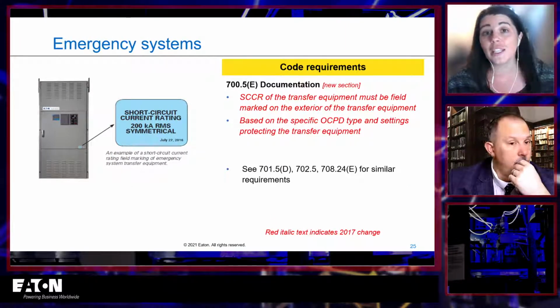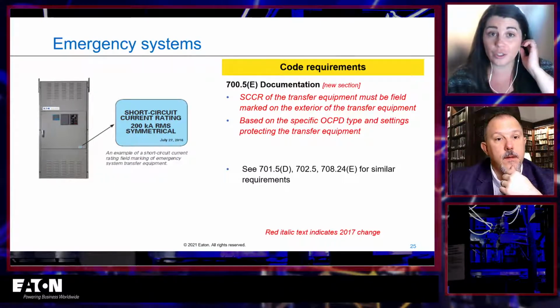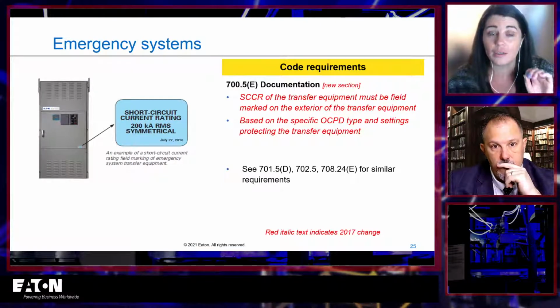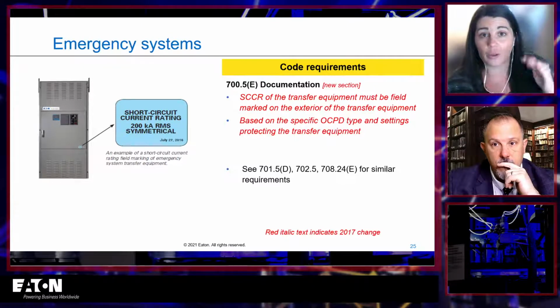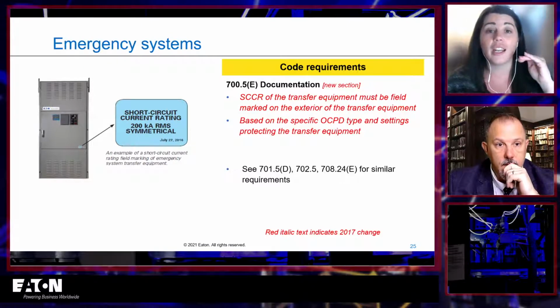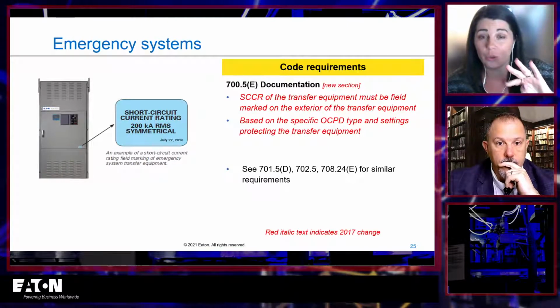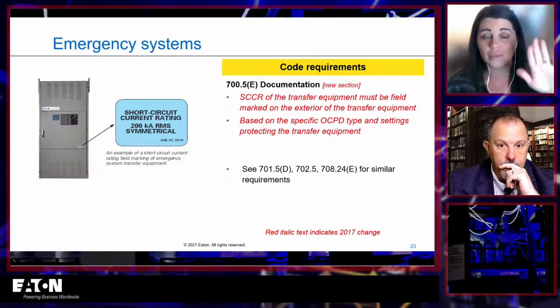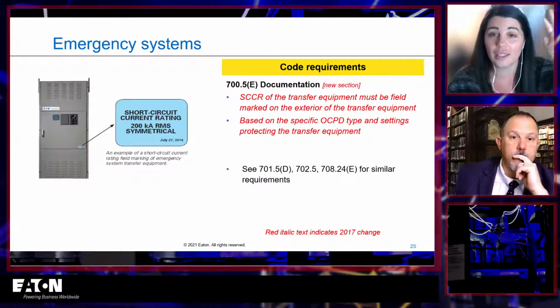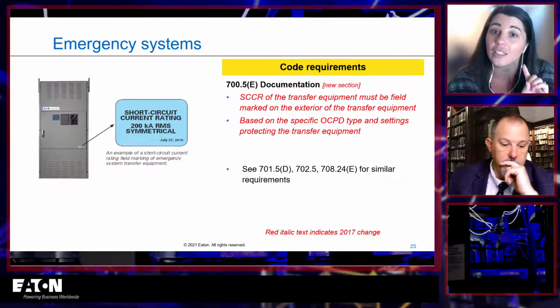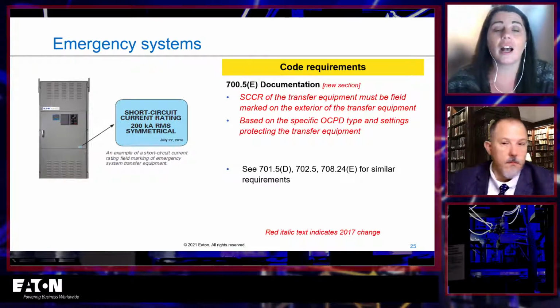And this one is a little bit different than the rest. This has to do with transfer equipment. So this is transfer equipment, think an automatic or a manual transfer switch. It is in 4 different sections of the code because it's in emergency systems, legally required standby systems, any of those systems that might have a transfer switch. So it's in multiple sections, but it's all the same thing. So I'm only going to show that to you once.